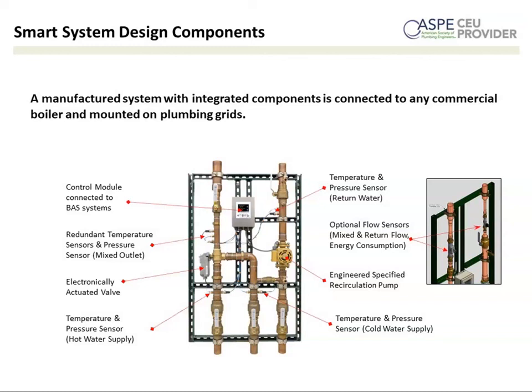And if you look to the very right, they're hard to see, but those are the flow sensors, which allow you the ability to monitor your outlet flow, your return flow, calculate your load flow, and then calculate your energy consumption. The unit does all this for you in BTUs and therms and gigajoules, whatever you choose that can be selected.